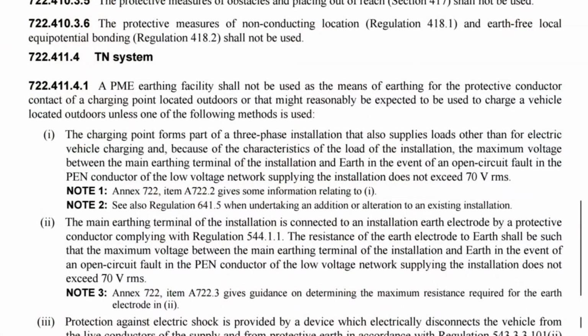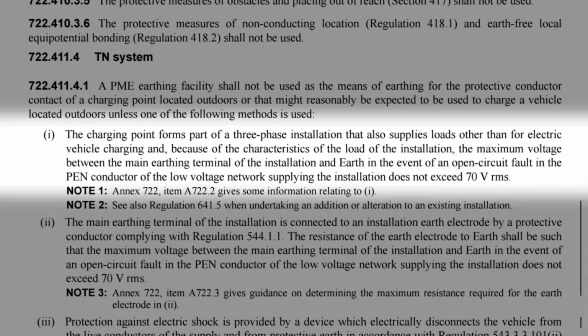But what about those PME systems? What changes then? Indent 1 states that you can connect an EV charger to a PME system if the charging point forms part of a 3-phase installation that also supplies loads other than for electric vehicle charging, and because of the characteristics of the load of the installation, the maximum voltage between the main earthing terminal of the installation and earth in the event of an open circuit fault in the PEN conductor of the low voltage network supplying the installation does not exceed 70 volts RMS.